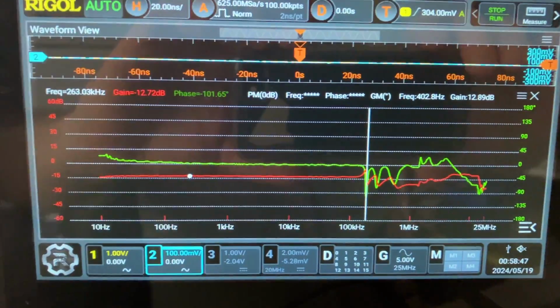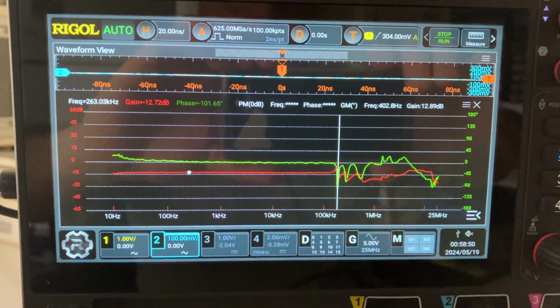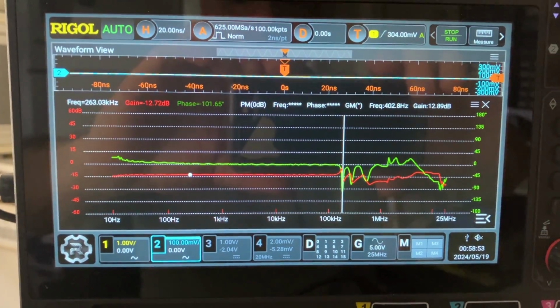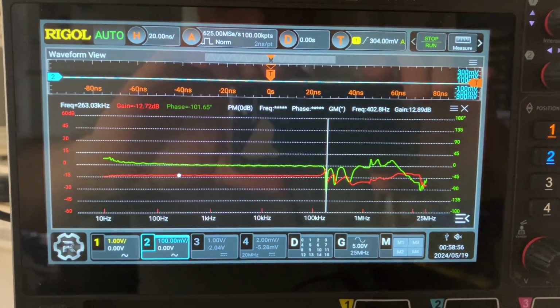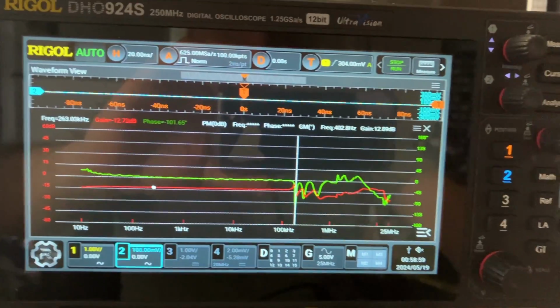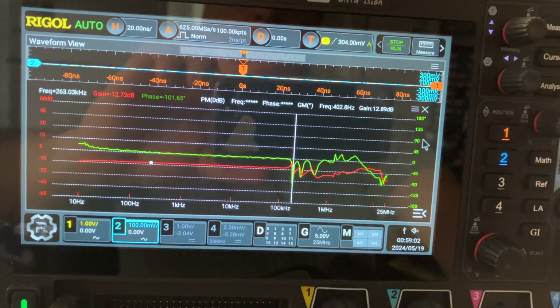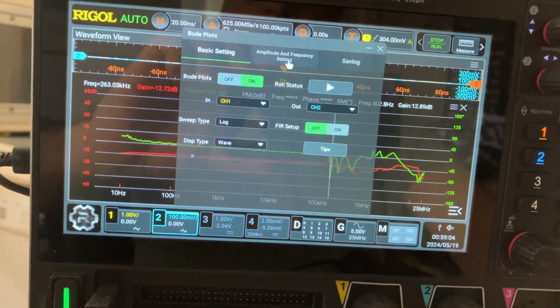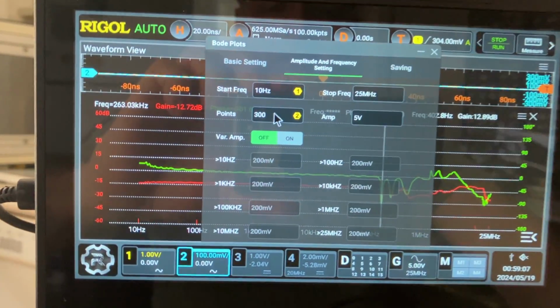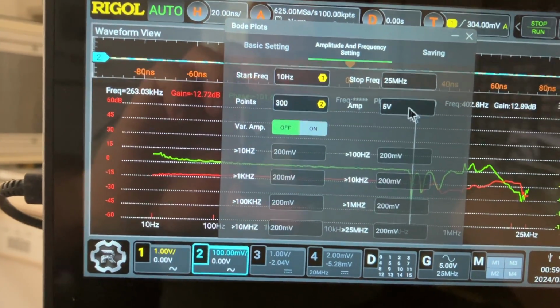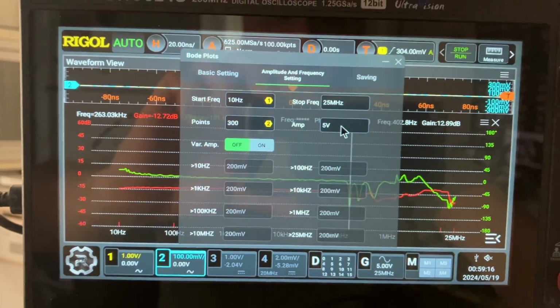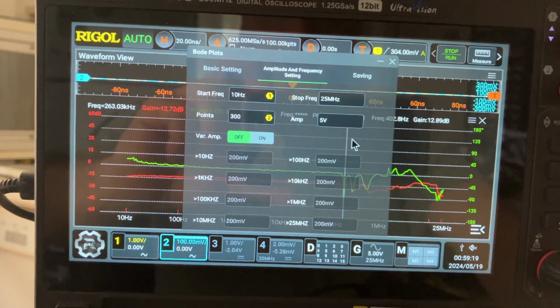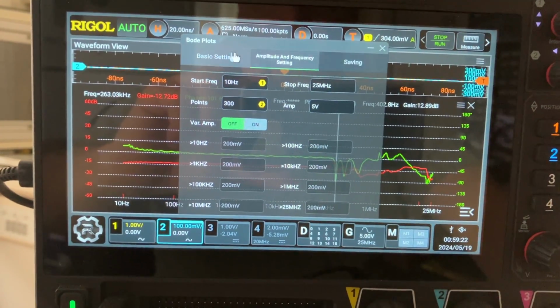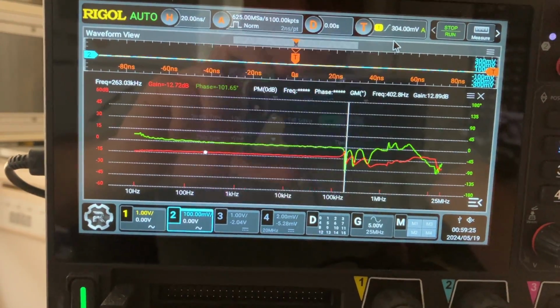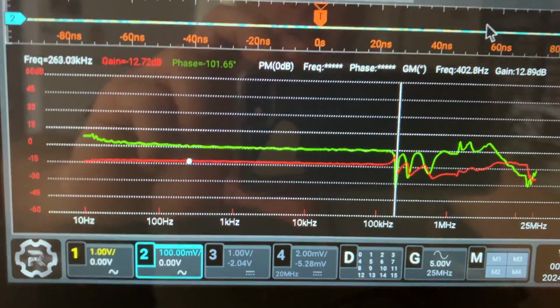And I was using this Bode plot function. It takes a long time. I was not sure if there was anything in the frequency response, so I put the maximum sampling points, let's click here to make this measurement, 300 points. So that's the maximum, 10 to 25 megahertz, which is maximum, and the amplitude also is maximum at 5 volt on the frequency generator. And it took something like 20 minutes to do all the measurement, but it was able to achieve it, and I'm very pleased with the results.